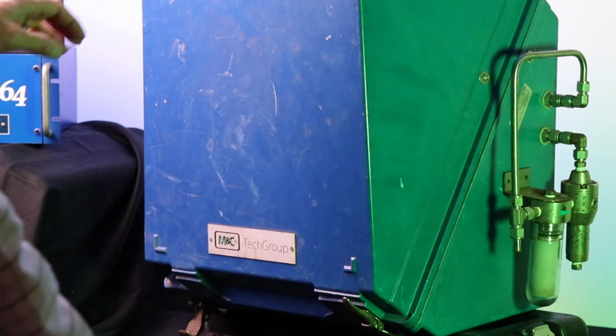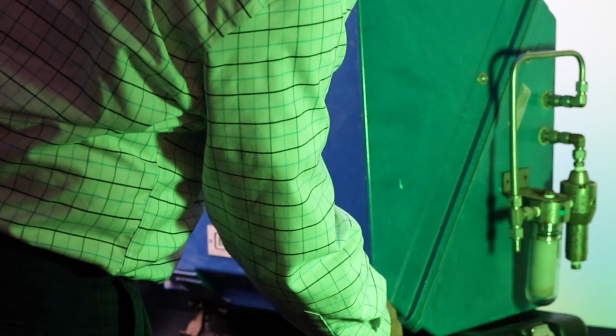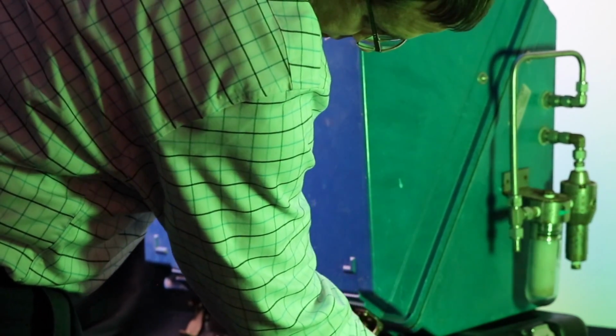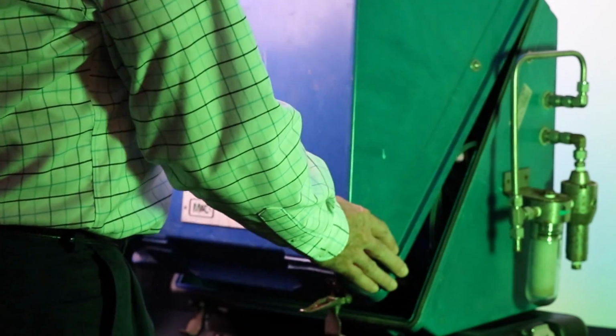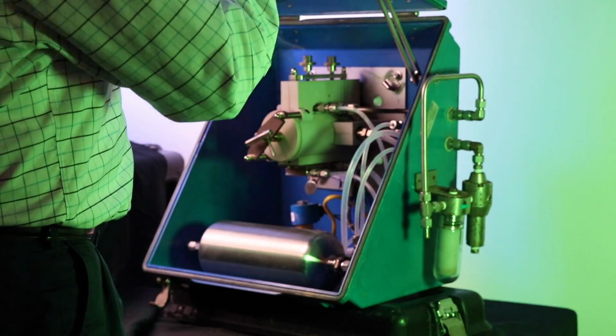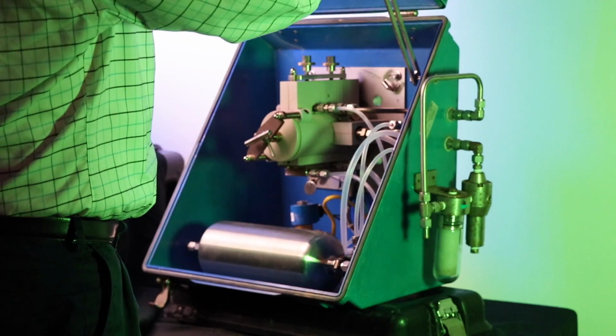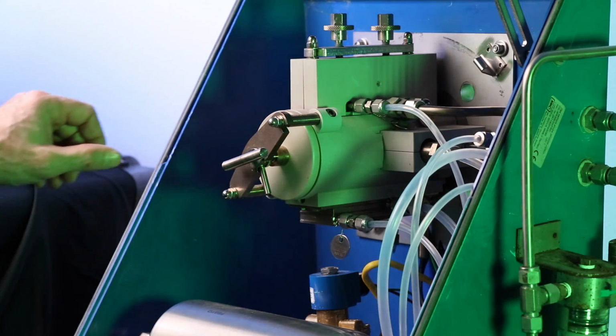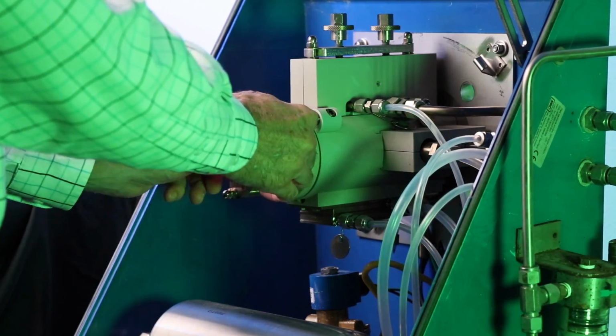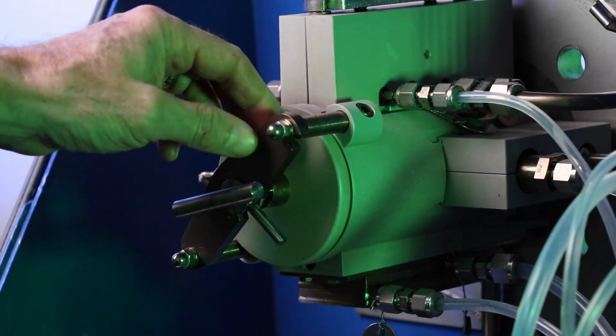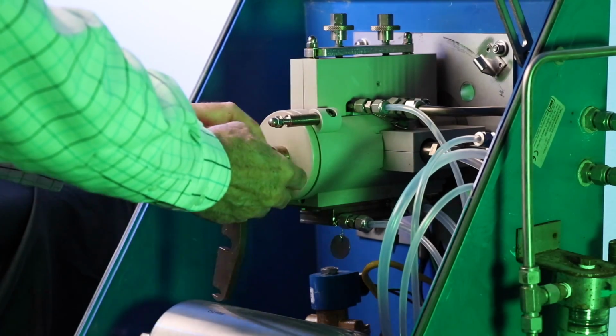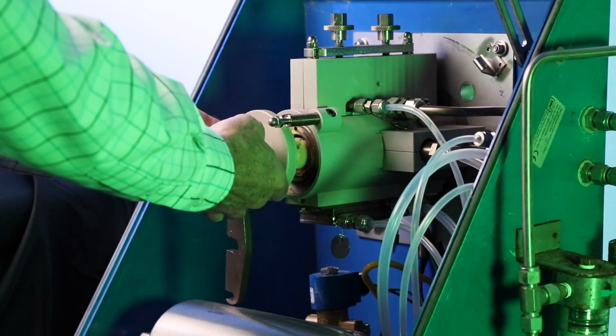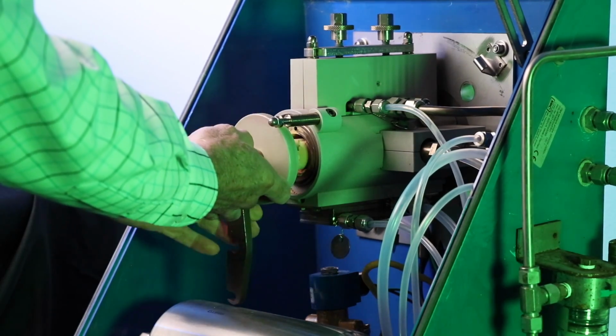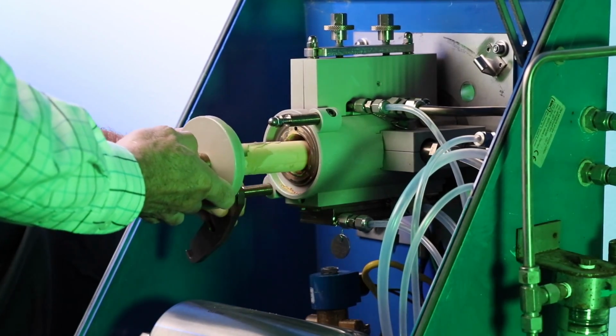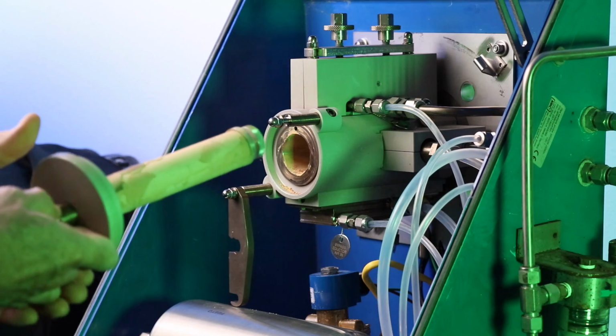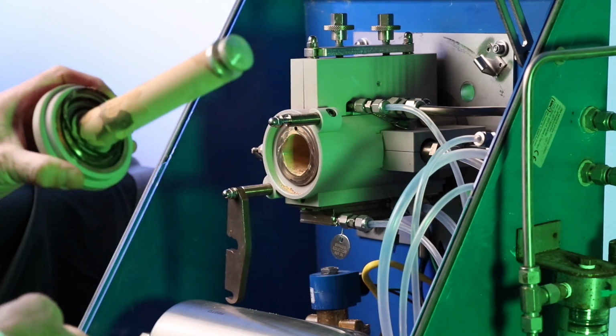Before beginning maintenance on the probe, remove the system from service and shut off the dilution air to the probe. Open the protective fiberglass clamshell by releasing the latches on the bottom. Loosen the strap bolt or T-handle on the filter lid assembly and rotate the strap out of the way. Gently pull on the filter pressing screw and remove the filter from the probe. You will now be holding the lid assembly.